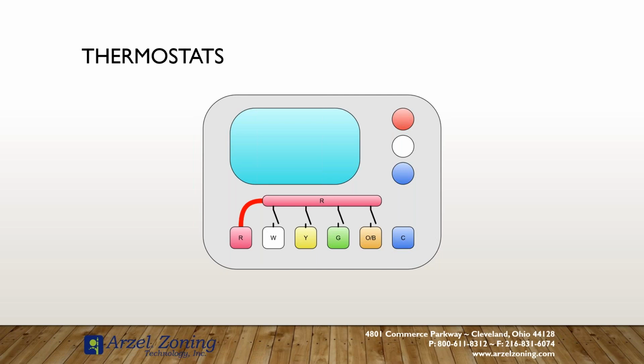A compounding problem typically means that there's more faults later on, and as we can test around the trouble that we found initially, we can then verify further points of operation that are causing us problems as well. So the place to start is with the thermostat. And the reason I say the place to start is with the thermostat is because you can't always be certain that thermostat you pulled off your truck is good.